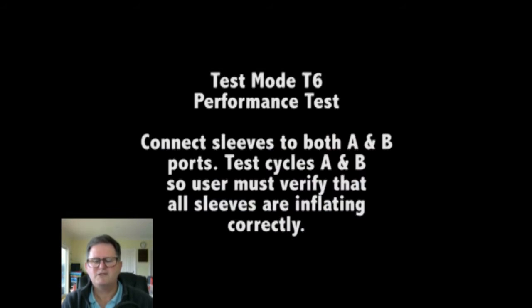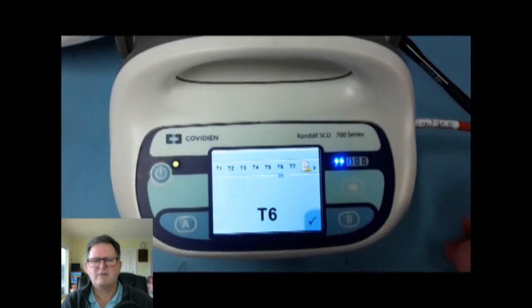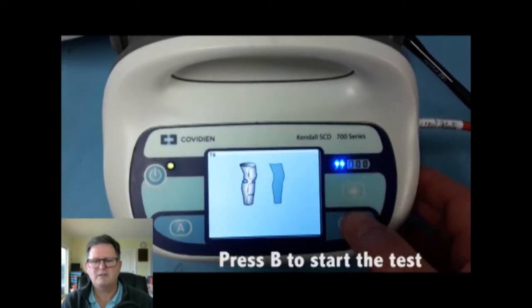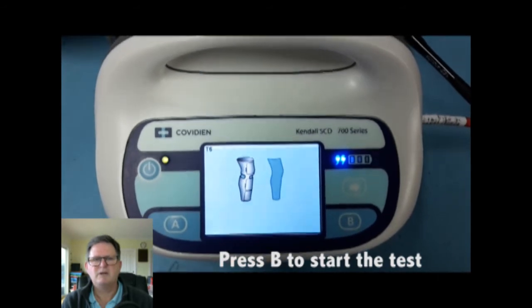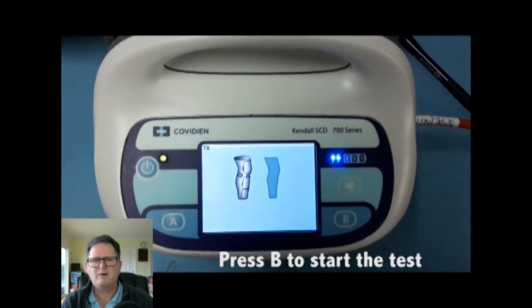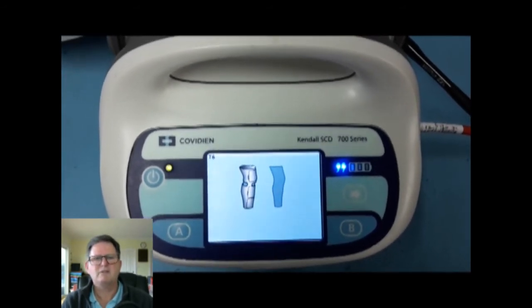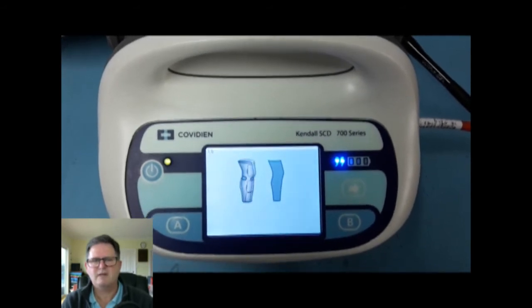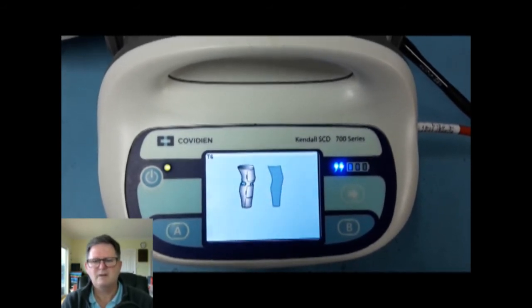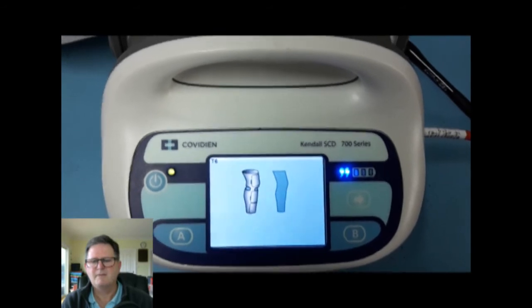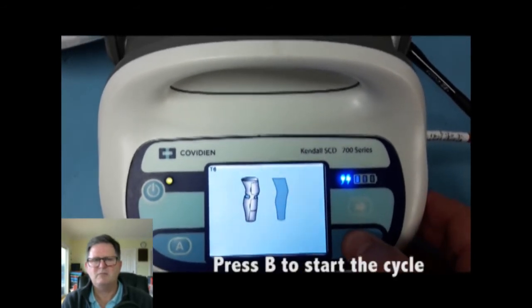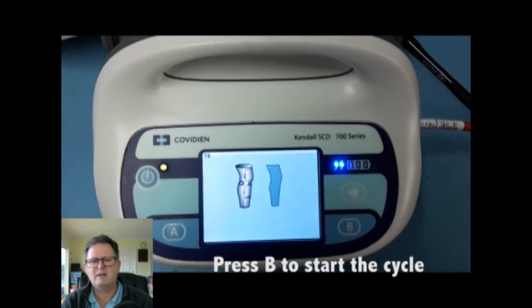T6 is a performance test. So here you'd connect up one or both sleeves with all the hoses and all that kind of stuff. Set it up on the bench and let it run through and just watch that it's doing what it should be doing. So this would be a good one to do in the workshop if you can't find anything obvious with it. Run it through this test and watch it inflating all the cuffs, your hoses. Make sure you've got no leaks. And if it passes this, well, you're pretty confident to send it back knowing that it's working.